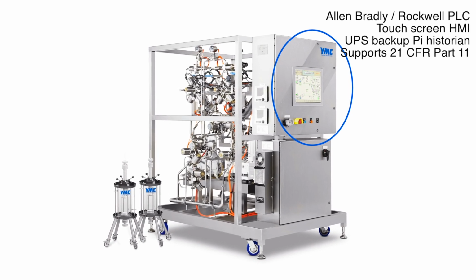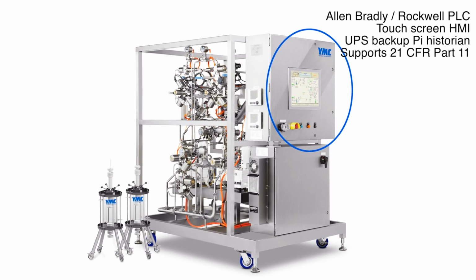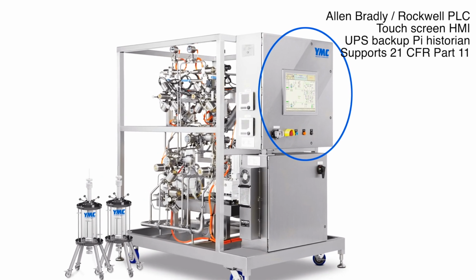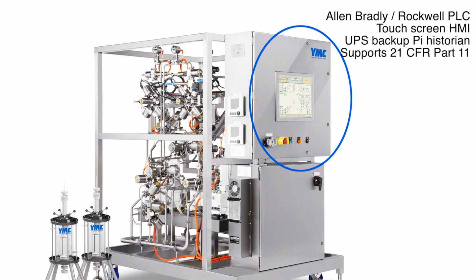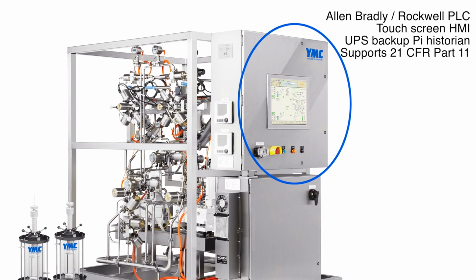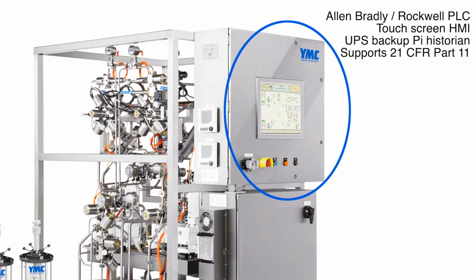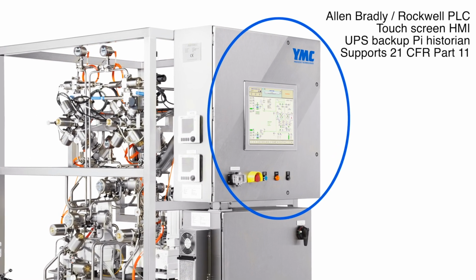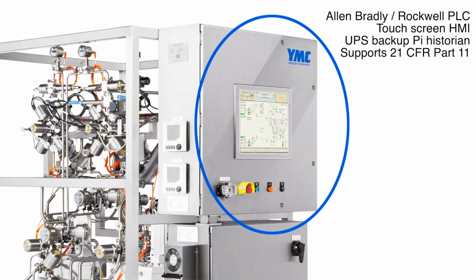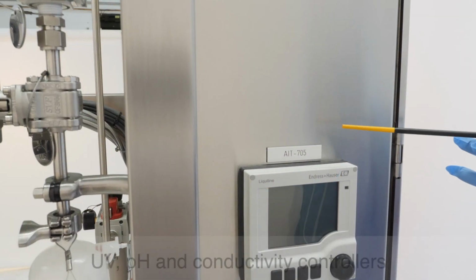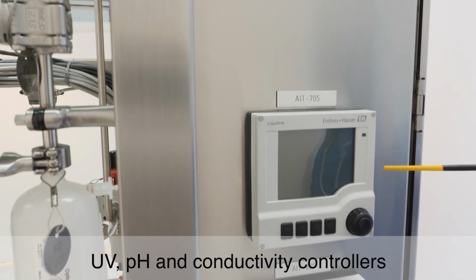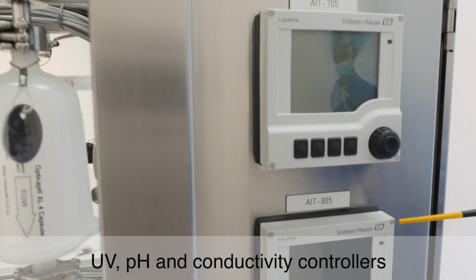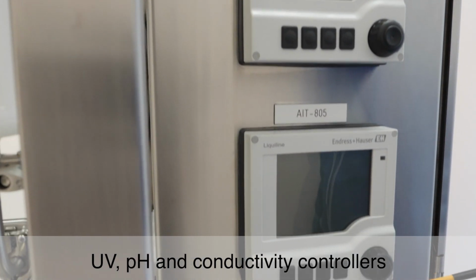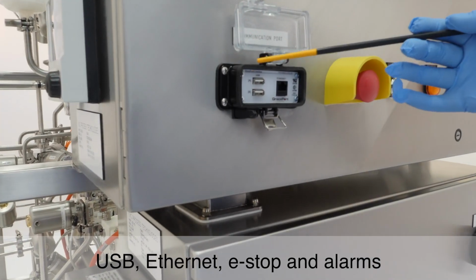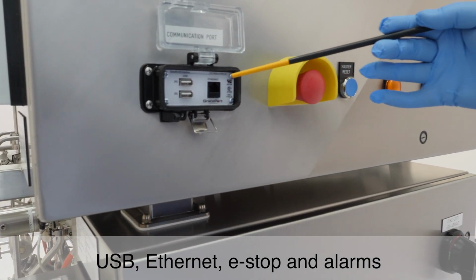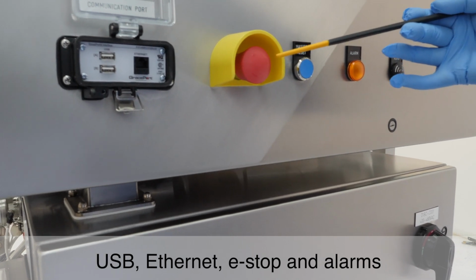The system is built on the Allen Bradley Rockwell automation platform and features a 20-inch touchscreen HMI, which can be linked to your preferred keyboard and or remote monitoring device. The PLC base unit has UPS backup and PI Historian, among other features that make this system support compliance to 21 CFR Part 11. On the side of the control panel, there are controllers for UV, pH, and conductivity sensors with a self-contained readout. They are handy for calibrating the detectors. In the front, there are dual USB ports and an Ethernet connection, as well as the e-stop, master reset button, and alarm indicators.